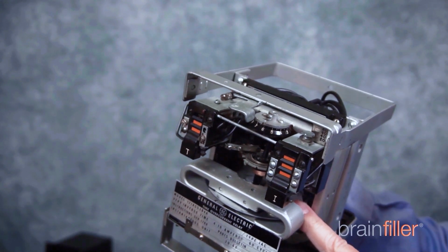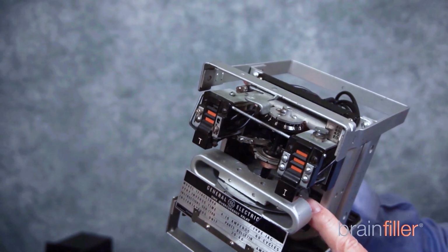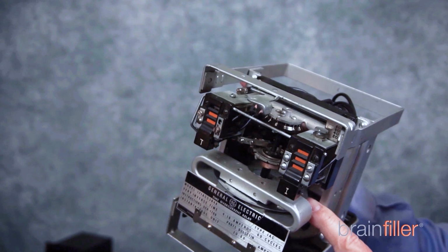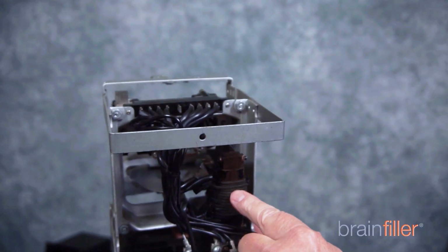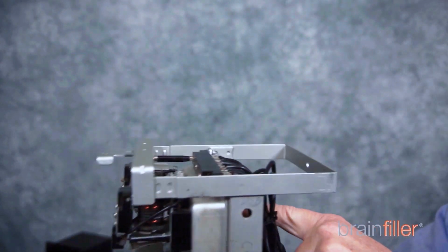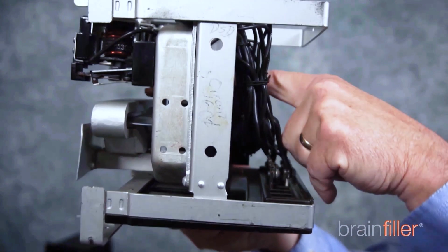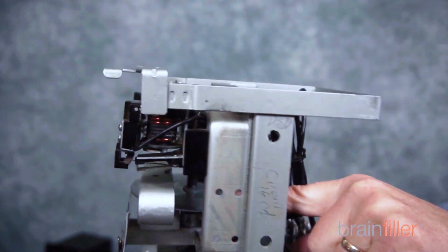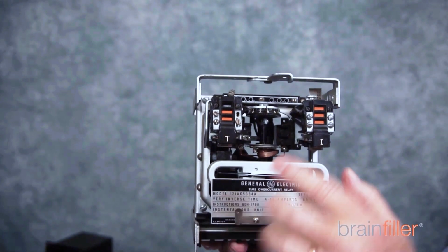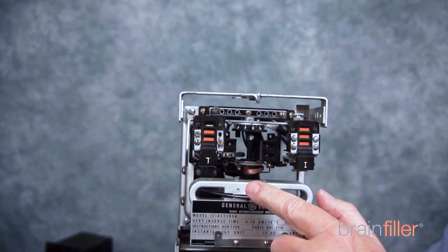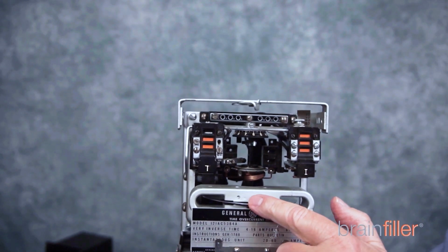And this disc in here is much like the disc in the old school analog watt-hour meters that would spin around. In fact, this coil back here is kind of C-shaped. It comes around, it's kind of hard to see, but it goes around this induction disc in here. So when the current exceeds the amp tap setting, then this disc is going to begin to rotate.